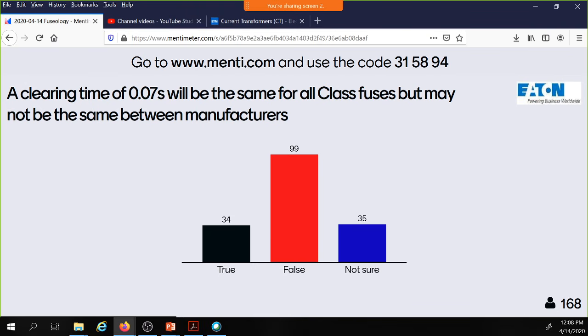And the message here, the 99 who have said false are in the right bucket. And the reason is, you're going to learn that even though I have a 100 amp or a 1200 amp fuse, remember it's 1200 amps and above, the different types of fuses, whether it be a different manufacturer or different model numbers within a single manufacturer, the trip curves are going to be different. So that 0.07 second clearing time for one fuse model and manufacturer is not going to be the same for a different fuse model and manufacturer. All right.